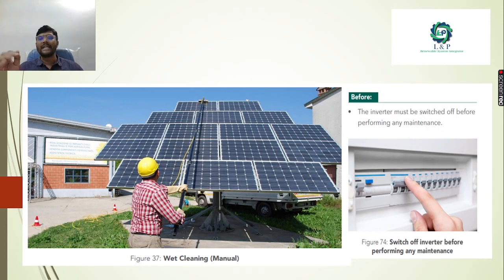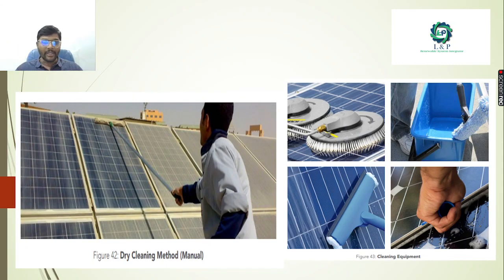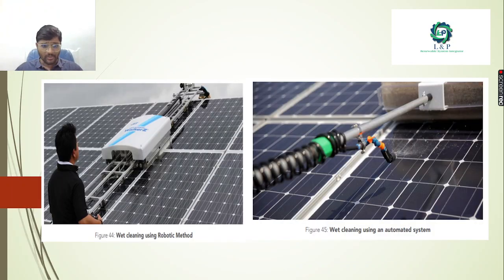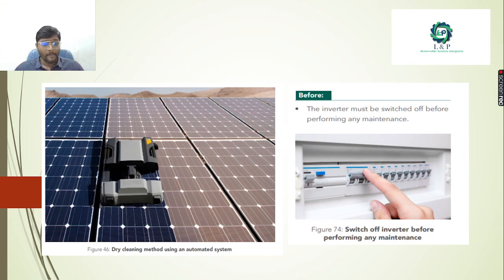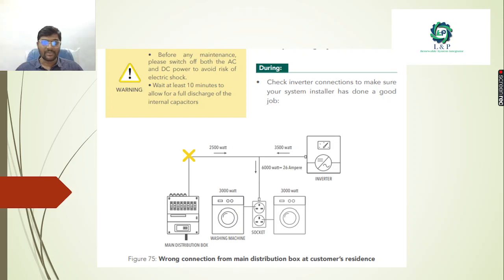And the next most important process of operation and maintenance is wet cleaning. You can do it manually. Before performing any sort of cleaning process, make sure the inverter is switched off before performing any maintenance activities. Then we can also perform dry cleaning methods. We can have the following cleaning equipment also. And if you're going for wet cleaning using the robotics method, you can use automated systems also. Even when you're performing automated methods, make sure you have switched off the inverter before doing any maintenance activities.